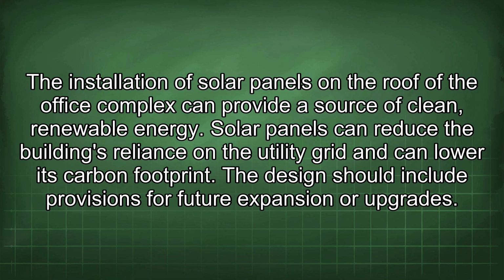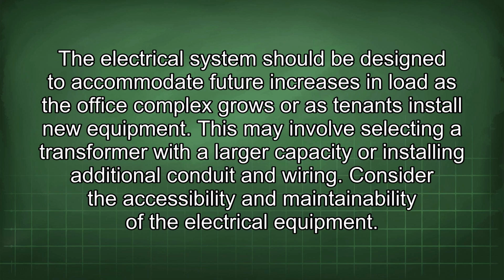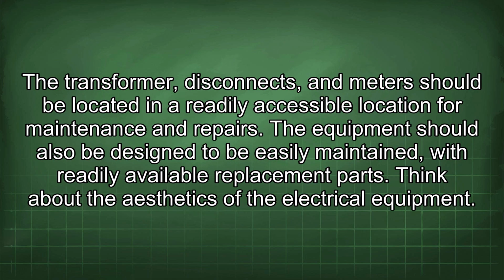The design should include provisions for future expansion or upgrades. The electrical system should be designed to accommodate future increases in load as the office complex grows or as tenants install new equipment. This may involve selecting a transformer with a larger capacity or installing additional conduit and wiring. Consider the accessibility and maintainability of the electrical equipment. The transformer, disconnects, and meter should be located in a readily accessible location for maintenance and repairs. The equipment should also be designed to be easily maintained, with readily available replacement parts.